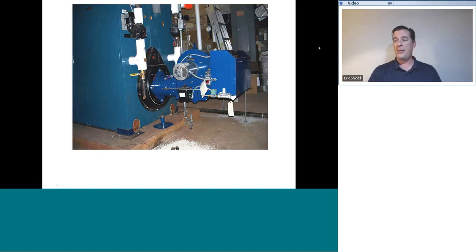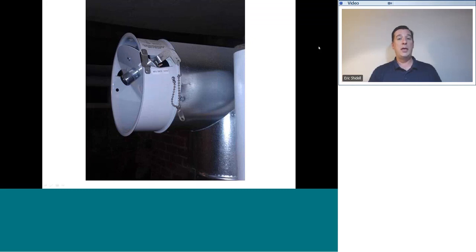Most of these burners are going to be equipped with a barometric damper. And the barometric damper serves the purpose to divorce the flue from the appliance. Remember, the flue is under negative pressure. It is sucking. And remember, as the wind blows across the top of that vent outside, it increases the strength at which it pulls on the vent. If that vent were directly connected to the appliance, it would also increase the strength at which it pulls through the heat exchanger of the appliance.